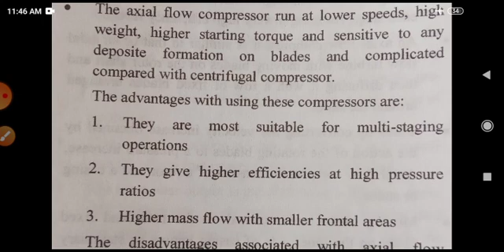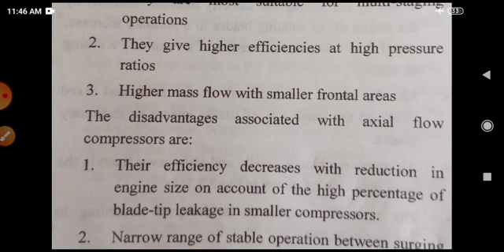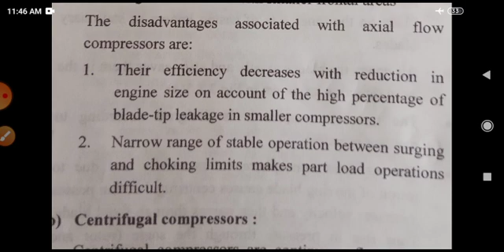The advantages of using this compressor are that it is most suitable for multi-staging operation. It gives higher efficiency at higher pressure ratios, and higher mass flow rate with smaller frontal area. Okay, these are the advantages of the axial flow compressor. Then let's see some disadvantages. Their efficiency decreases with engine size on account of a high percentage of blade tip leakage in smaller compressors. The narrow range of stable operation between surging and choking limits makes part load operation difficult.